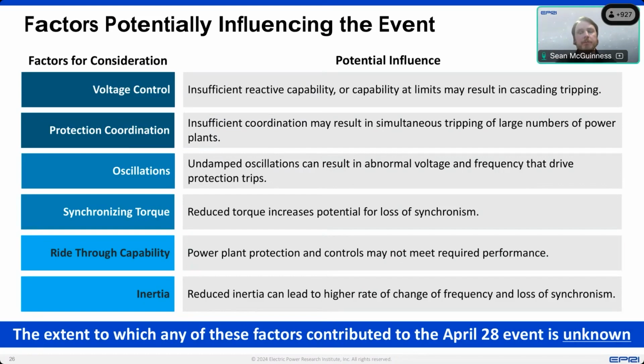Something we saw from the 2021 event, and we've seen in other grids as well, is around protection coordination. Usually that's transmission grid protection coordination, but what we've seen here is that through interconnection requirements and grid codes, we set fault ride-through envelopes for voltages. And within those, we might say that you need to remain connected from 0.88 per unit voltage up to 1.1 per unit voltage for a certain amount of time, maybe a second or more. And then on the power plant side, they don't see that as the minimum. They see that, well, if I'm going to set my overvoltage protection, what's my requirement, and set a small margin to that.